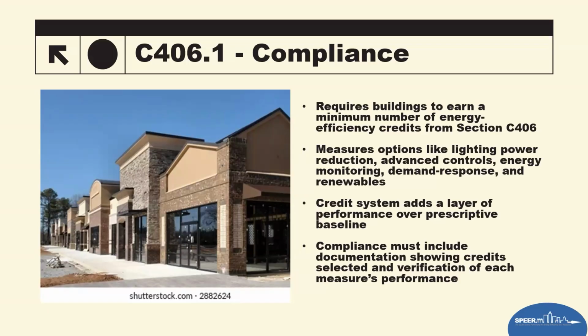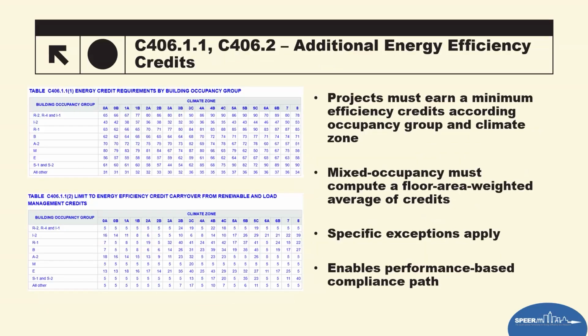So instead of just meeting the minimum prescriptive requirements, commercial buildings now must earn a defined number of credits by selecting from a menu of efficiencies and load management processes or measures. This encourages basically early integration of design decisions. So you'll need to pick what credits your projects are pursuing, ensure that they're documented, and verify that the measurements are being performed. Part of the shift here is from purely component by component compliance to system and performance awareness compliance. Instead of just picking each component, they're now looking at it from a performance, holistic aspect. And then additional efficiency credits as well.